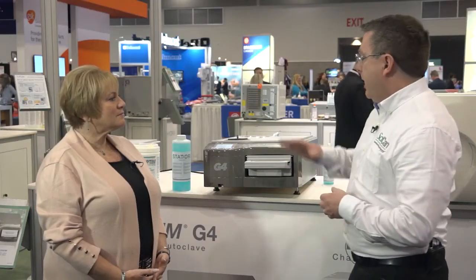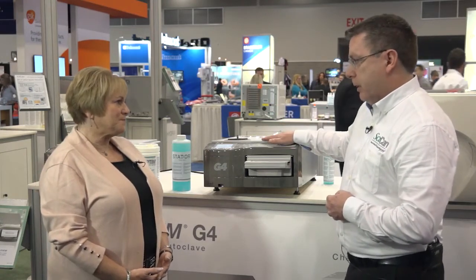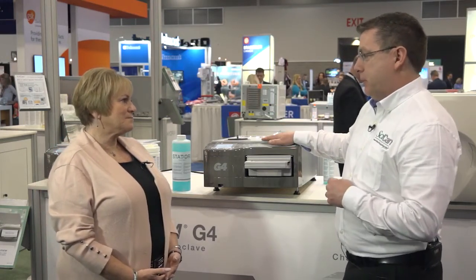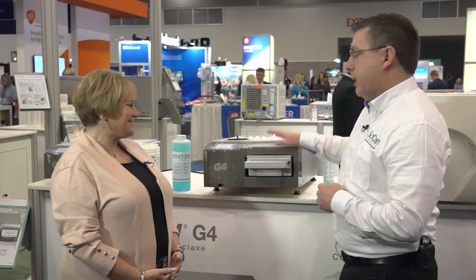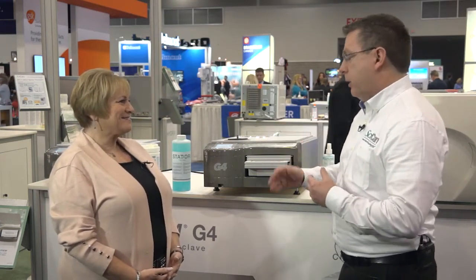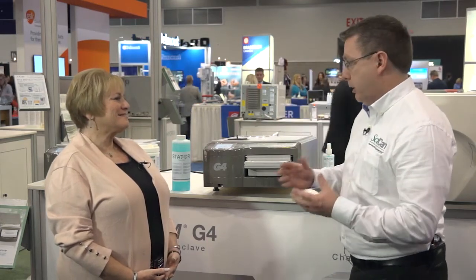What it also does, if anything was to go wrong with the STATIM, is automatically email the factory itself. We could then contact the office and say, hey, you've got this error code, can you check these 3 items to make sure that they're functioning properly? If they can't find the problem, with their permission, they'll give us a code on the screen and we'll take control of the machine from Toronto. We'll then test every single individual component from Toronto, and if there is something wrong, we will contact their service technician and say, please go out to Dr. Smith's office with this part to solve the problem. So instead of having 2 or 3 service calls, we can get it all accomplished in one.